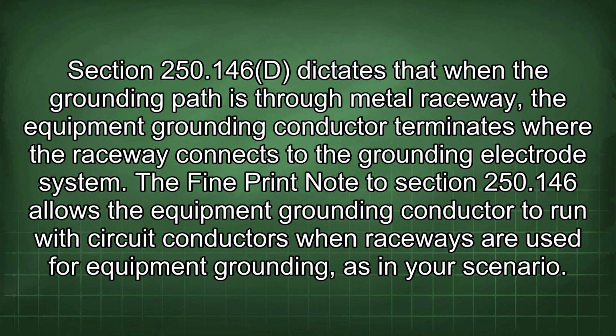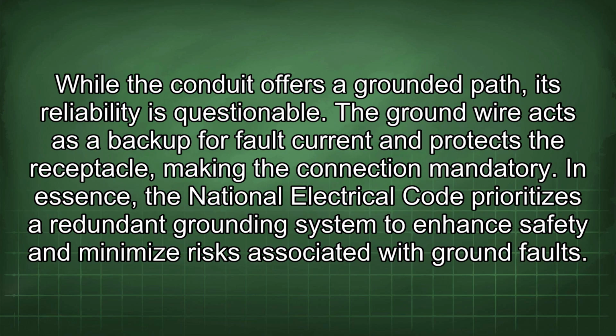Section 250.146d dictates that when the grounding path is through metal raceway, the equipment grounding conductor terminates where the raceway connects to the grounding electrode system. The fine print note to Section 250.146 allows the equipment grounding conductor to run with circuit conductors when raceways are used for equipment grounding, as in your scenario. While the conduit offers a grounded path, its reliability is questionable. The ground wire acts as a backup for fault current and protects the receptacle, making the connection mandatory.